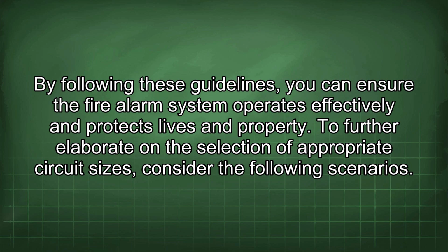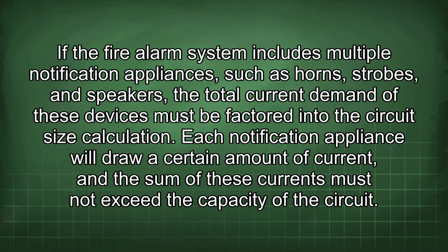By following these guidelines, you can ensure the fire alarm system operates effectively and protects lives and property. To further elaborate on the selection of appropriate circuit sizes, consider the following scenarios. If the fire alarm system includes multiple notification appliances such as horns, strobes, and speakers, the total current demand of these devices must be factored into the circuit size calculation.